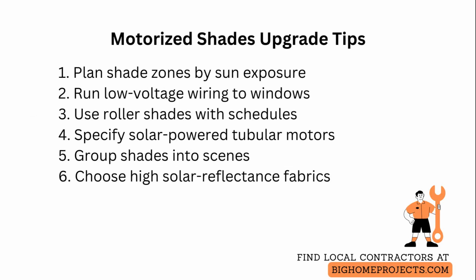Start by planning shade zones based on sun exposure and room use to minimize wiring complexity and maximize control. For new construction, run low-voltage wiring to each window, rough opening, and plan conduit to central control locations so motors and sensors integrate cleanly with the electrical and automation systems.